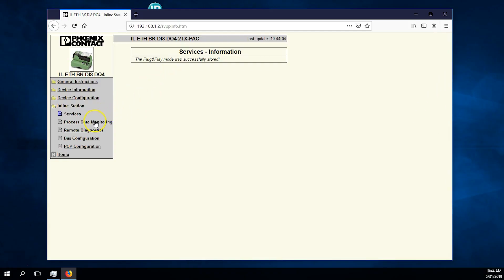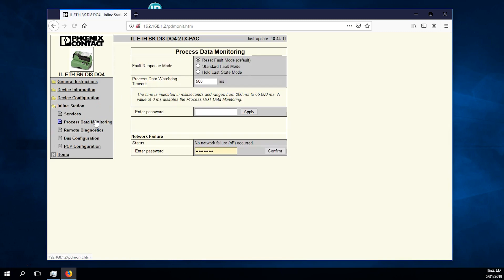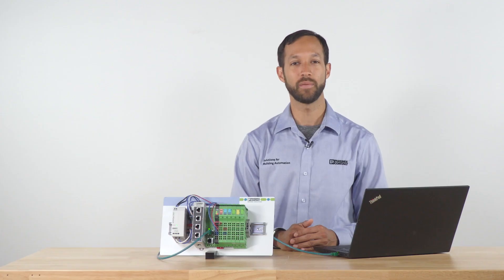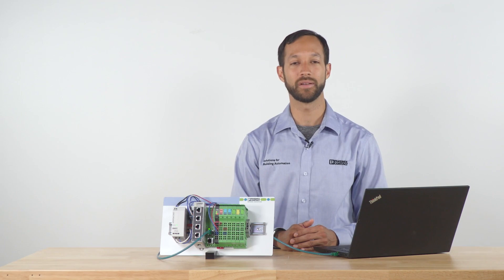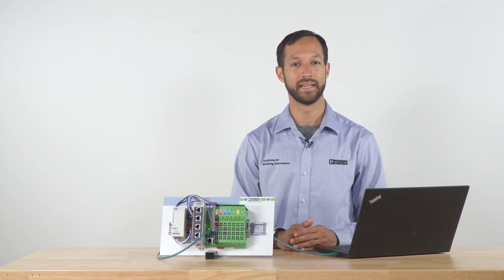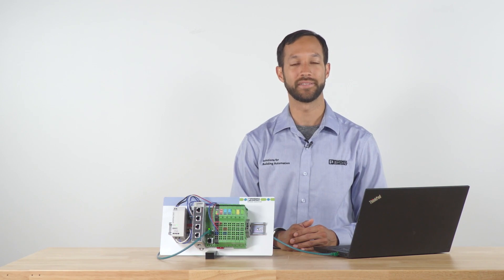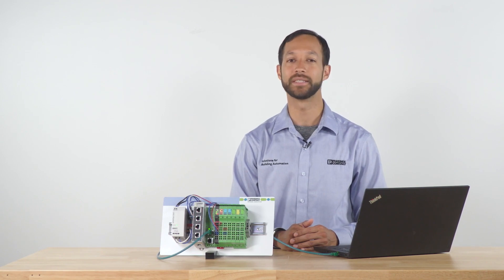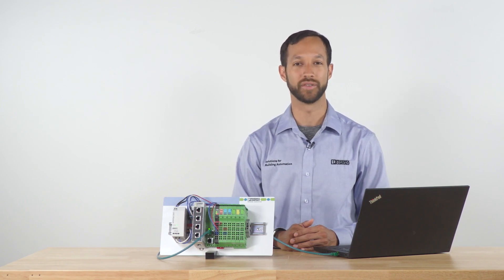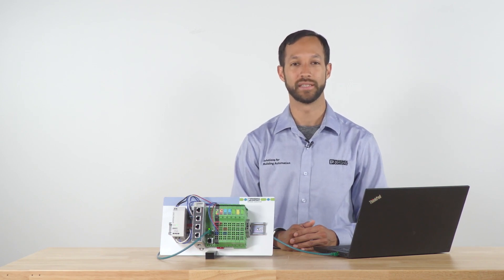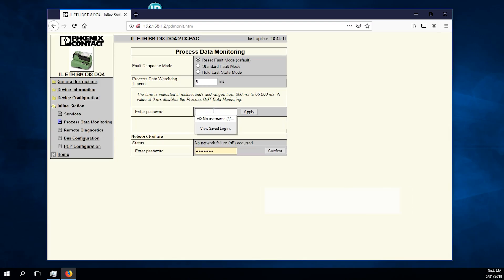Now navigate to process data monitoring. Set fault response mode to reset fault mode and the watchdog timeout to zero milliseconds. The zero milliseconds timeout is primarily for development purposes. In the actual launching of a station, you typically want to set it to five times the polling rate of your station. Enter private as the password and hit apply.